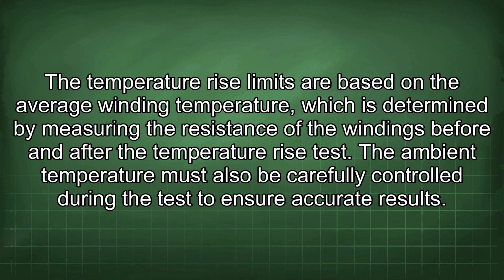The temperature rise limits are based on the average winding temperature, which is determined by measuring the resistance of the windings before and after the temperature rise test. The ambient temperature must also be carefully controlled during the test to ensure accurate results.